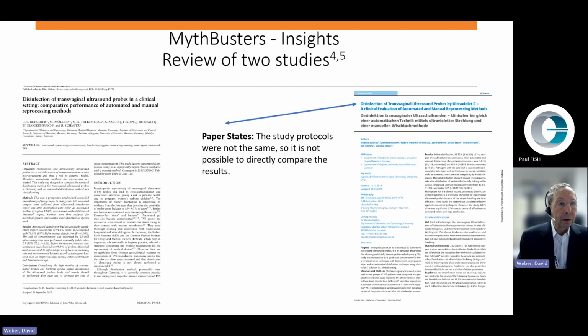Now, finally, Mythbusters in review of 2 studies. On the left, you see disinfection of transvaginal ultrasound probes in a clinical setting, comparative performance of automated and manual reprocessing methods. On the right, disinfection of transvaginal ultrasound probes by UVC, a clinical evaluation of automated and manual reprocessing methods. The study protocols between these papers were not the same, so it's not possible to directly compare the results of the data in these 2 studies. Again, if you're going to compare data between 2 studies, they have to use identical methodologies.